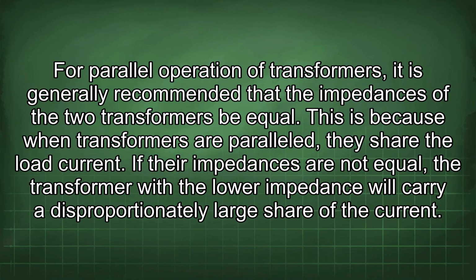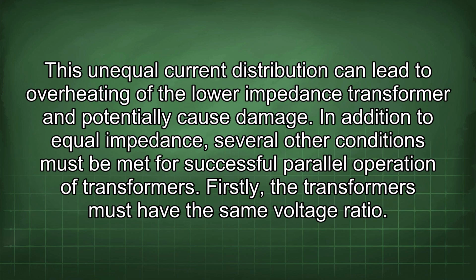For parallel operation of transformers, it is generally recommended that the impedances of the two transformers be equal. This is because when transformers are paralleled, they share the load current. If their impedances are not equal, a transformer with the lower impedance will carry a disproportionately large share of the current. This unequal current distribution can lead to overheating of the lower impedance transformer and potentially cause damage.